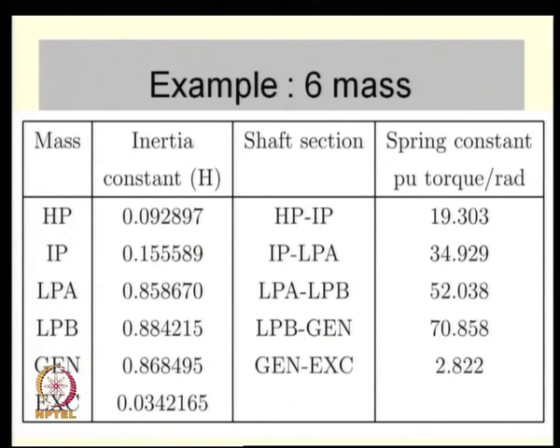How do you take out the frequencies? Let us look at this turbine generator system in isolation, not connected to the electrical network. Let us assume damping is zero — it is not zero, but it is quite small and difficult to estimate. So damping from purely mechanical sources is assumed to be zero, and let us see what are the modal properties of this particular system.